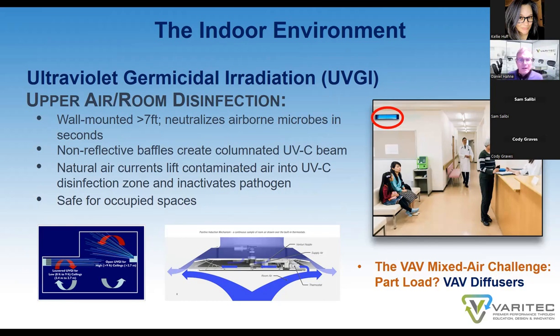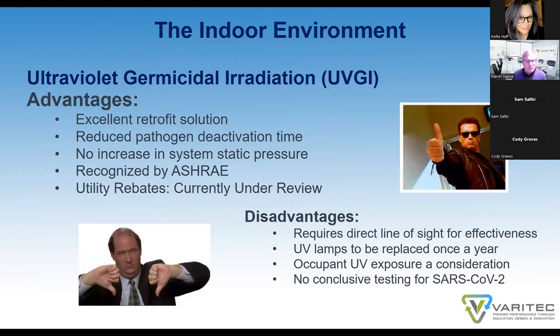Being exposed to UV light is a health concern, but the way these units are devised and built, that should not be a concern. So anyway, it is a technology to be considered, certainly for strategic places in buildings and zones and areas that could be subject to higher levels of infection. So the advantages of ultraviolet germicidal irradiation are that it's an excellent retrofit solution that can be put into conference rooms, emergency rooms, mounted in supply air ducts, and mounted in air handler coils to prevent the crossover of any pathogens released in a space that are drawn into a return air grill.